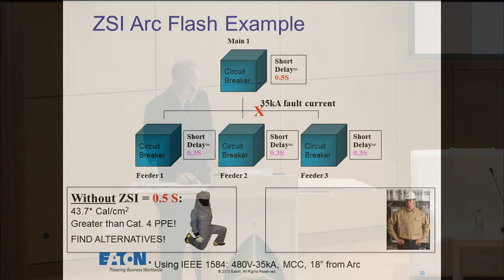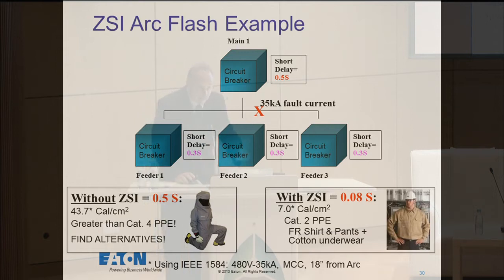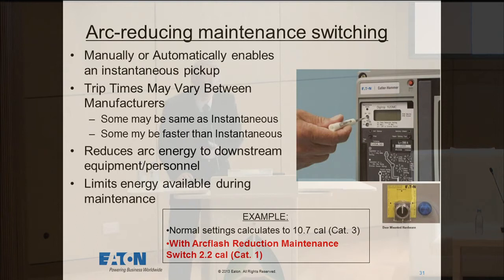So that's without zone selective interlocking. With zone selective interlocking, again, this is the communications between the two. This upstream breaker is going to go as fast as he can. As fast as he can in this particular situation is 0.08 seconds. So we've dropped the time down drastically here, and with that, we've dropped the corresponding energy. The energy level comes down to 7 calories. So this is the difference between putting on a full moon suit and putting on a flame retardant shirt and pants. Much easier for the worker. In fact, in many installations in the United States in the petrochem industry, the everyday workwear is a Category 2 flame retardant shirt and pants. So this is an example of what zone selective interlocking can do to help you with arc flash. There are some other technologies that have been developed to also help you with arc flash, and these are in several types of UL listed circuit breakers.